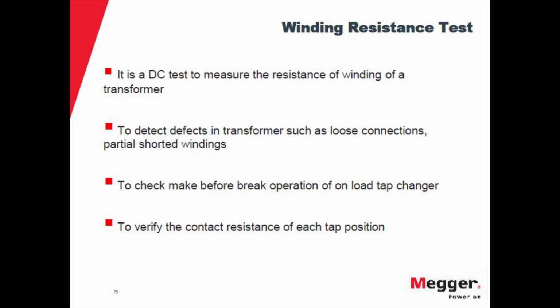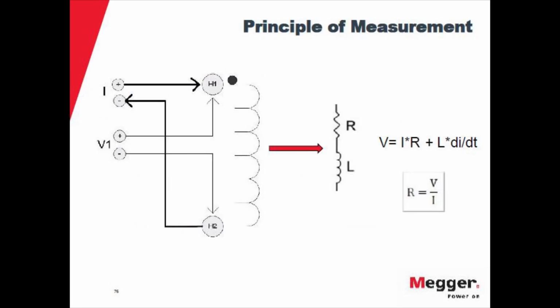This is also a very basic test, but here is where you have a little bit of complication due to the inductance. So you apply a DC current through the winding, and you measure the voltage drop across the winding. But this winding has the inductive part. For that, now you're interested in this portion of the equation, but then you have the inductive part that depends on the current variation in time.